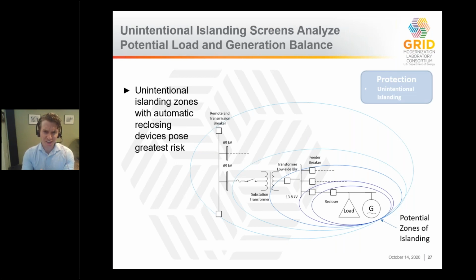We're on the unintentional islanding slide, and the question came up on the last presentation of whether inverters are capable of forming islands or other generation. When inverters are in grid connected mode, or any DER for that matter, it's important from a safety and power quality perspective to assure that DER won't energize a part of the line that's disconnected from the system, unless it's intentionally designed to do so in a community microgrid or multi-user microgrid approach. So flagging the potential for load and generation to be matched, where an island could occur, is another threshold that's commonly applied. Next slide, please.